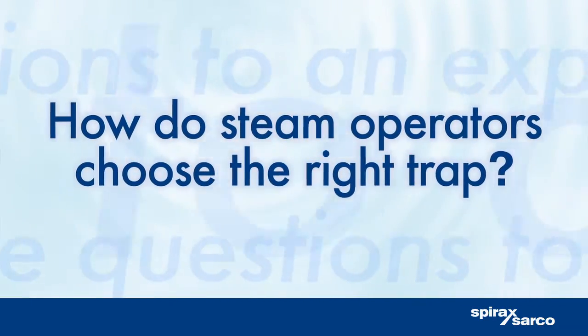How do operators choose the right trap? Picking the right steam trap for the job is not always straightforward, and it is really worth seeking advice. It depends on the application. If there is a lot of starting and stopping, then a thermostatic steam trap would be a good choice. On the other hand, an application with varying loads is best served with a mechanical trap, because it responds quickly to changing loads.